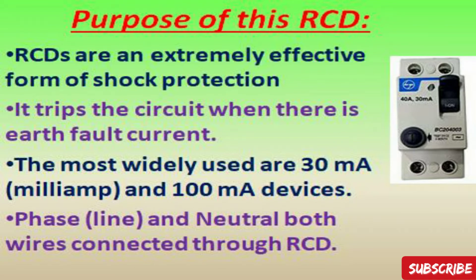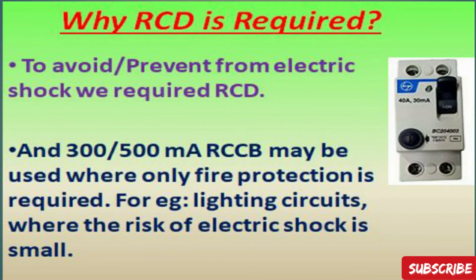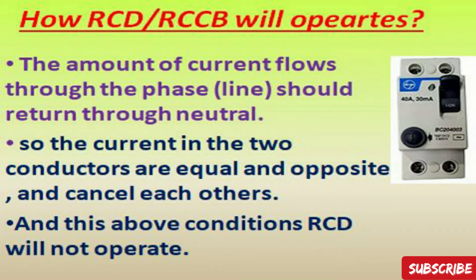Why is RCD required? Generally, the human body has a high resistance, so if somebody accidentally touches a live conductor, a very small current will flow through the body — not enough to trigger a fuse or MCB — and that person may get a severe injury. To prevent electric shock, we require an RCD. Also, 300 to 500 milliamps RCCBs may be used where only fire protection is required, for example in lighting circuits where the risk of electric shock is very small.